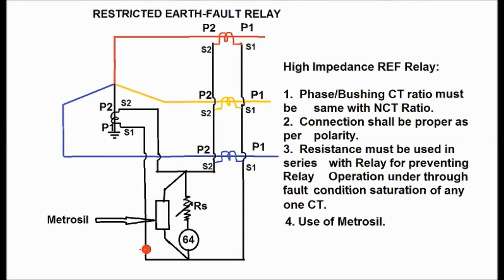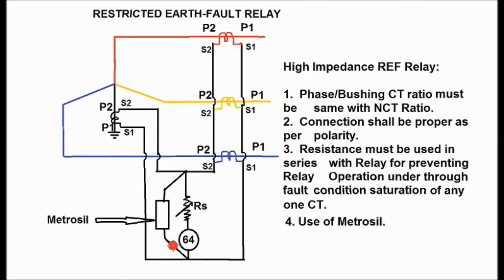For the secondary side formation: S1 of the neutral CT is connected together with S1 of all the phase CTs. S1 of the red, yellow, and blue phase CTs are shorted together and also shorted to the neutral CT S1, forming one terminal. S2 terminals of all the bushing CTs and the neutral CT are shorted together to form another terminal, and these two terminals are taken by cable to the control and relay panel.